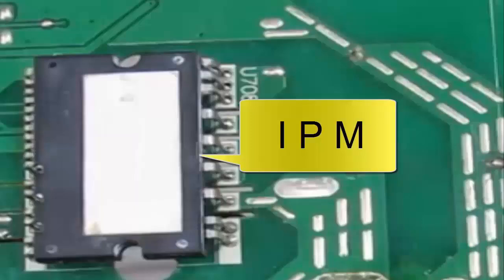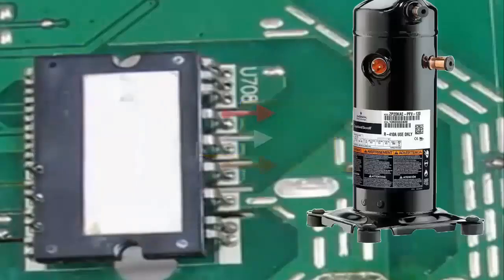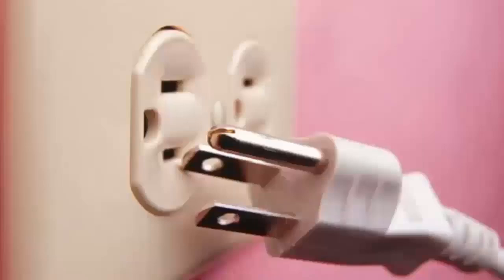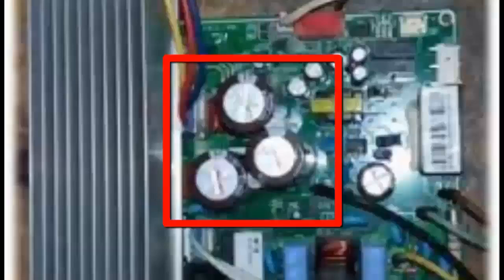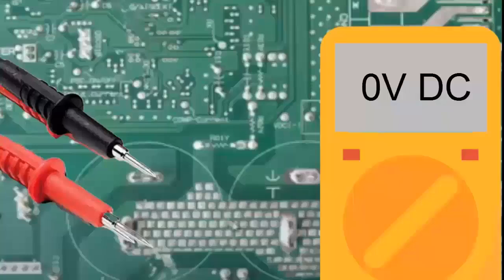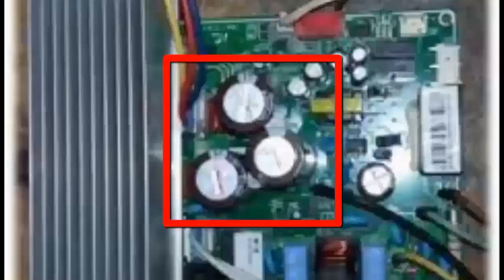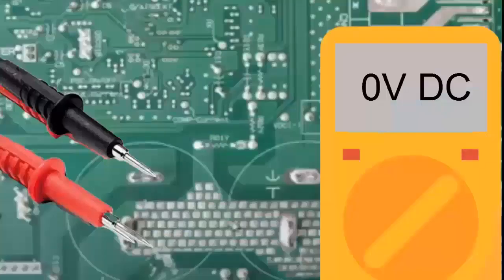The IPM electronic module is used in inverter-type AC control boards to supply power to the compressor. Before performing any test, disconnect the unit from the power supply. High-voltage capacitors can store dangerous energy even after the unit is unplugged. To check if capacitors are discharged, use a multimeter in DC voltage mode. Place the probes across the large capacitors. The reading should be close to 0 VDC. If they still hold a charge, wait or safely discharge them.